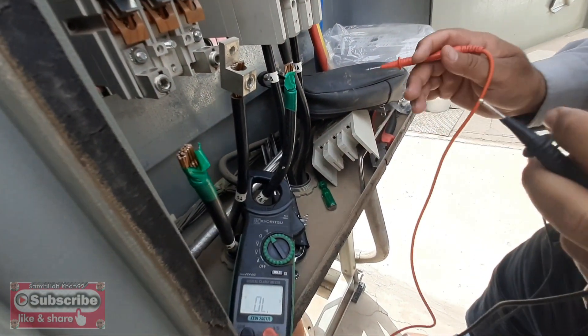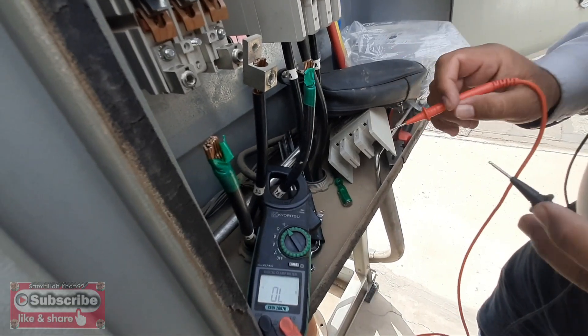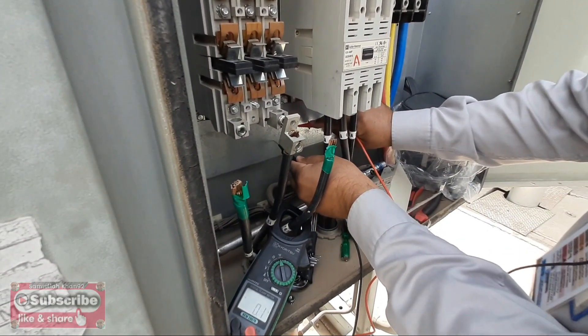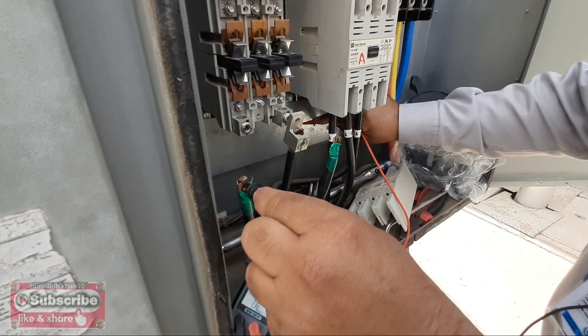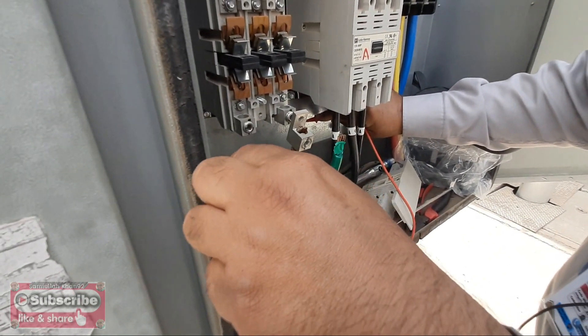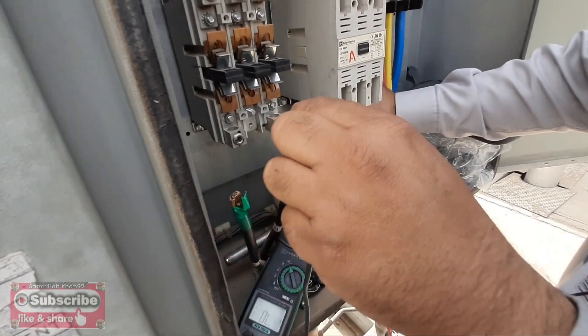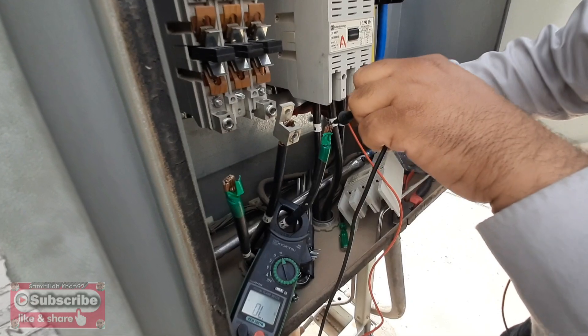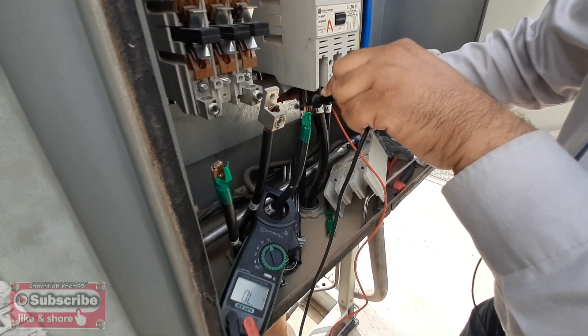Now we check the ground of the compressor against the body. You can see no beep is coming from the ground check. Line one is not grounded — that's okay. Line two is also okay, and line three is also okay. This means our compressor is in good condition with no problem in the winding.